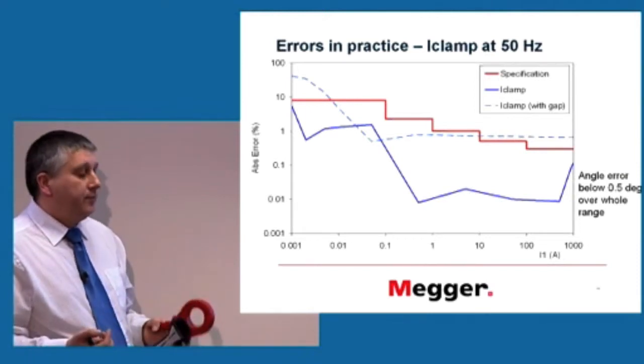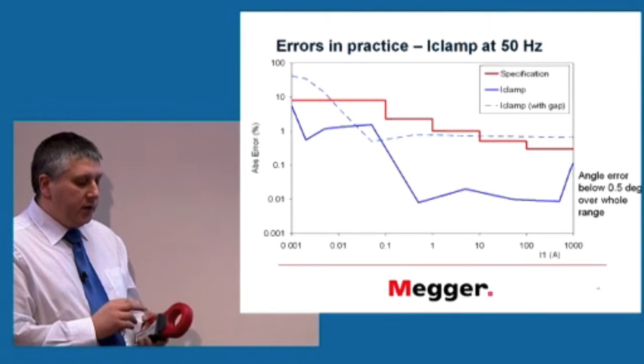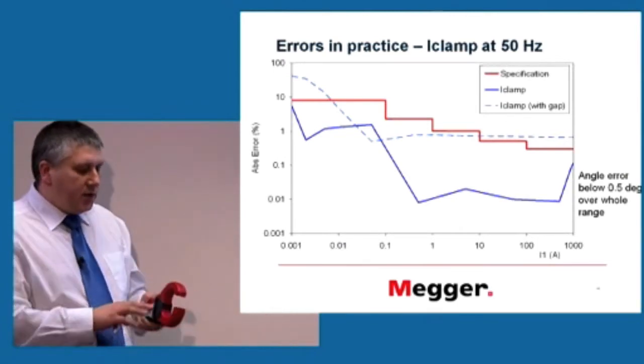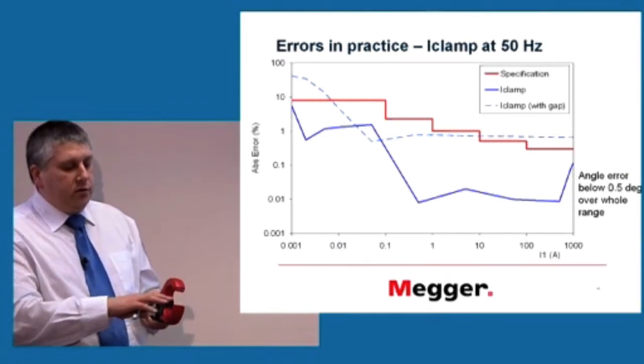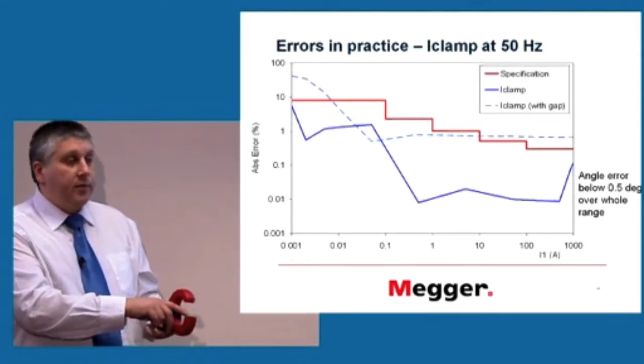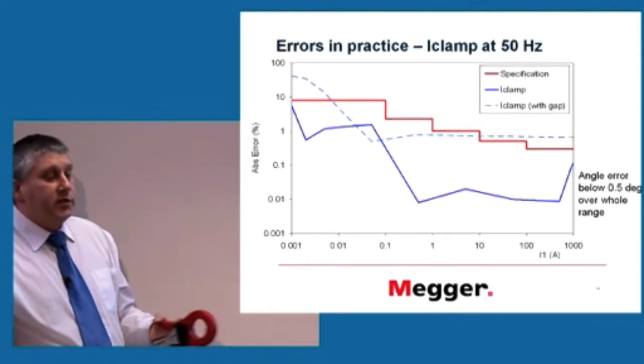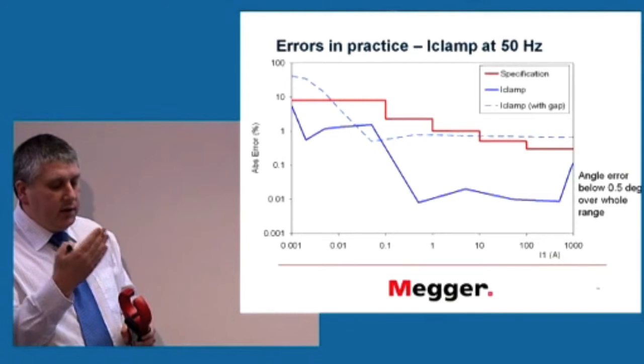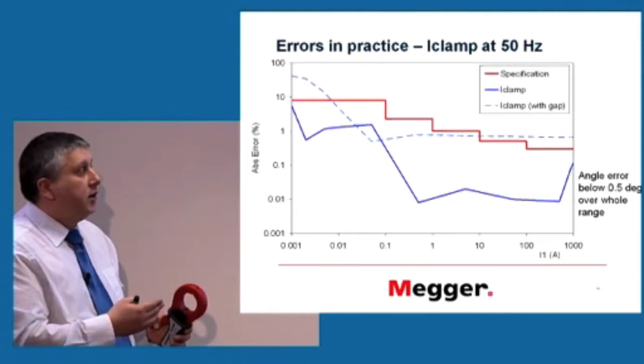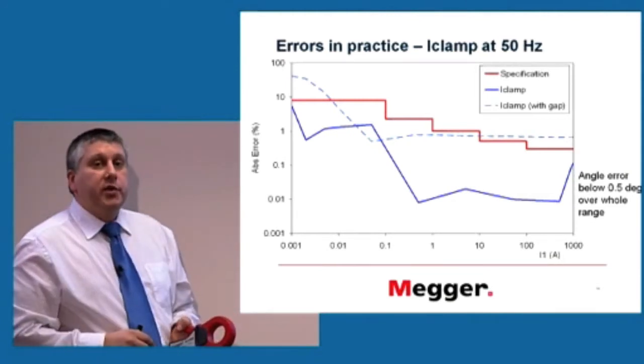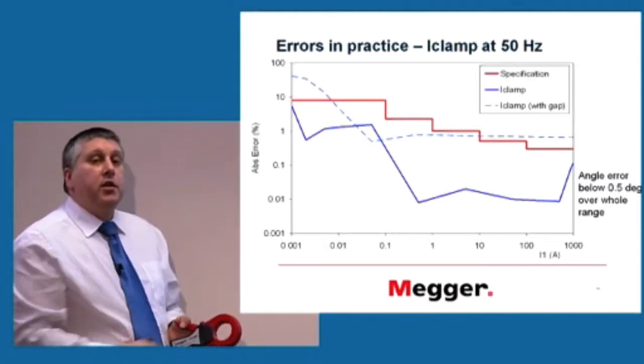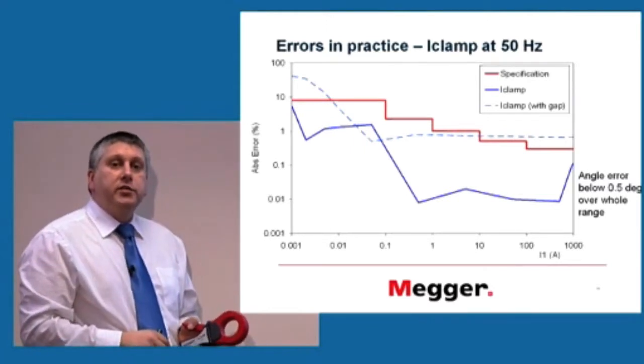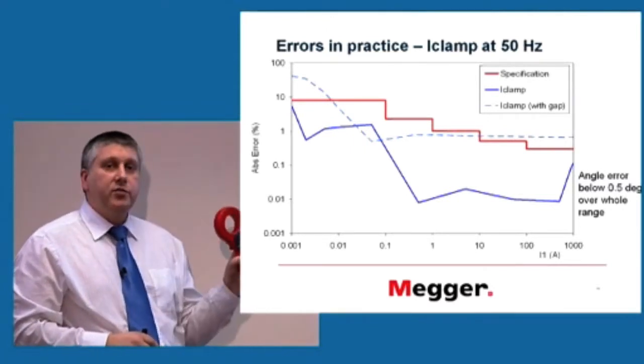However, because there's a magnetic core involved, if we clamp this around something and there's a bit of dirt or sand or perhaps a squashed bag at the surface, which will introduce some air gap between the cores, then that will impact the measurement accuracy. And we can see that it no longer holds to specification at high currents. And the users have to be aware of that.